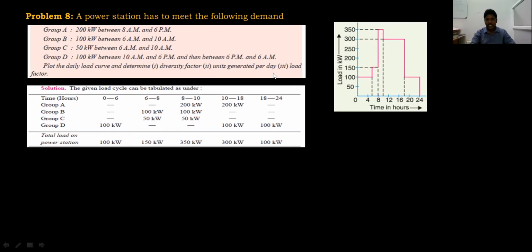The number of units generated is the area under the load curve, as we discussed in the last problem. In the same way, we continue and find the area under the load curve. That gives you the units generated. It is a very easy process. And what is the next problem? Load factor is average load by maximum demand. I already told you, the number of units generated divided by 24 gives you the average load. Therefore, average load divided by maximum demand gives you the load factor.